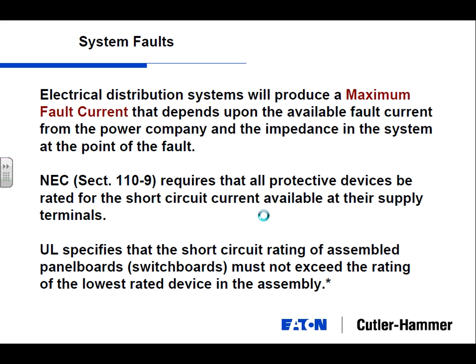So at this point, I'm a long way from that transformer that's sitting at the end of the block. If it's 65,000 amps available there, by the time a fault occurs here, there's so much impedance through the system that maybe I'm only at 3,000 amps fault current here. And that's one of the key design elements. If you're starting and designing, whether it's a consultant or a design-build contractor, that is one of the most important elements to take into the design. Also, that factors into cost.